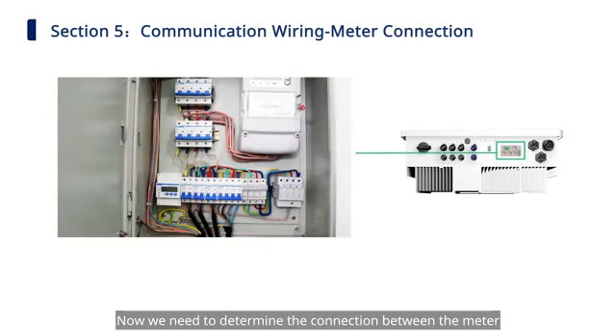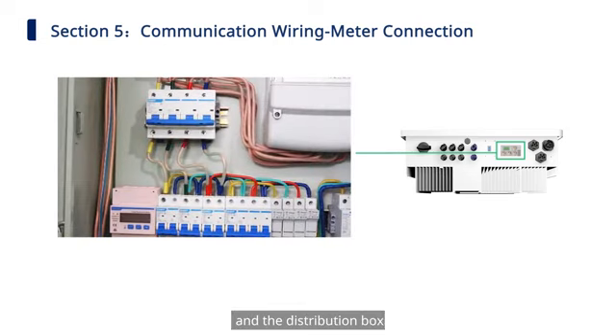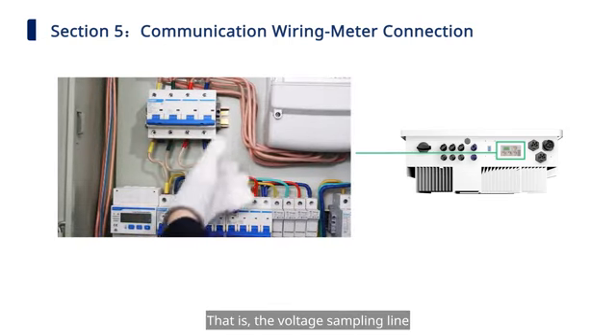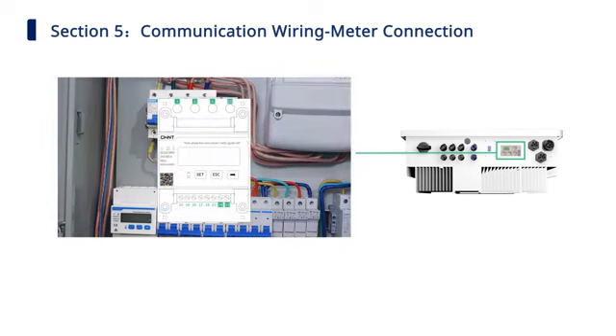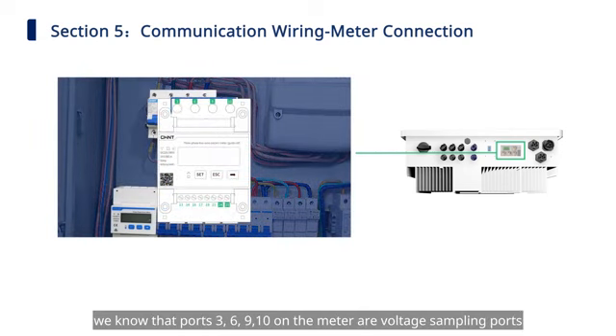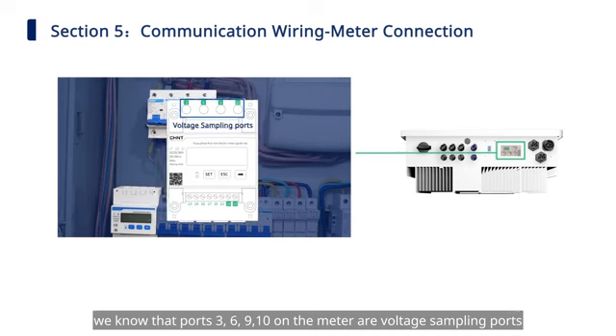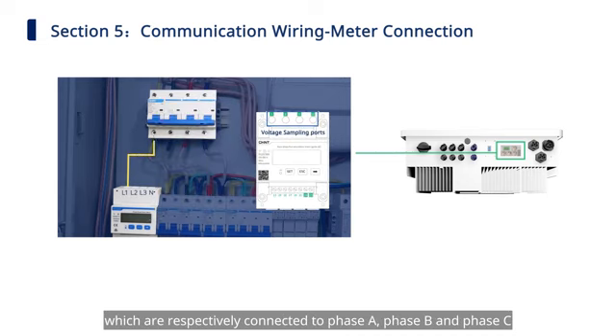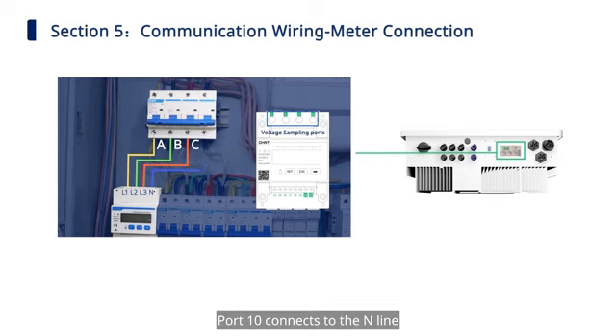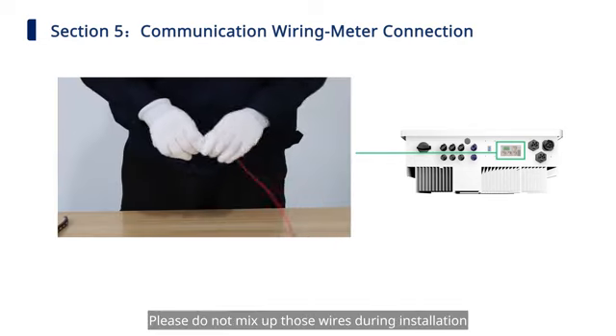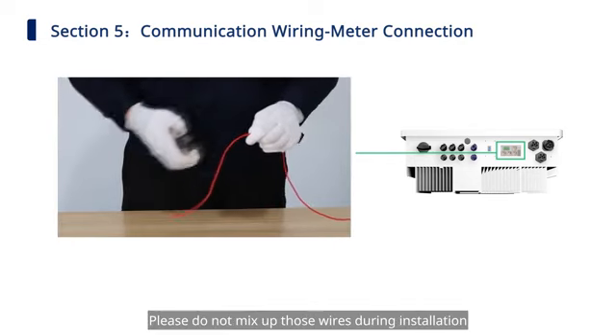Now, we need to determine the connection between the meter and the distribution box, that is, the voltage sampling line. From the picture, we know that ports 3, 6, 9, 10 on the meter are voltage sampling ports, which are respectively connected to phase A, phase B, and phase C. Port 10 connects to the N line. Please do not mix up those wires during installation.